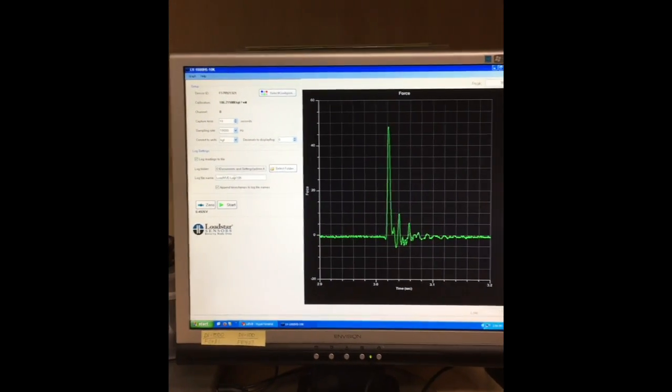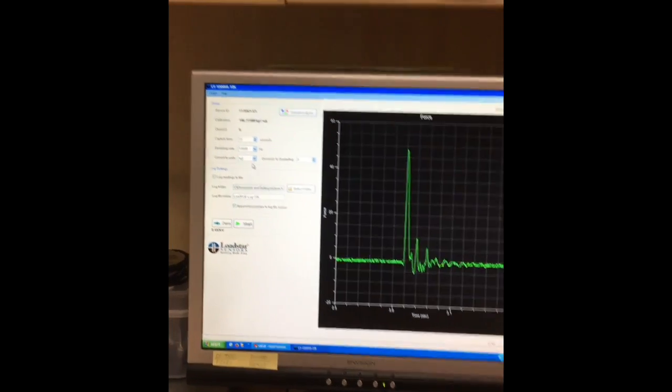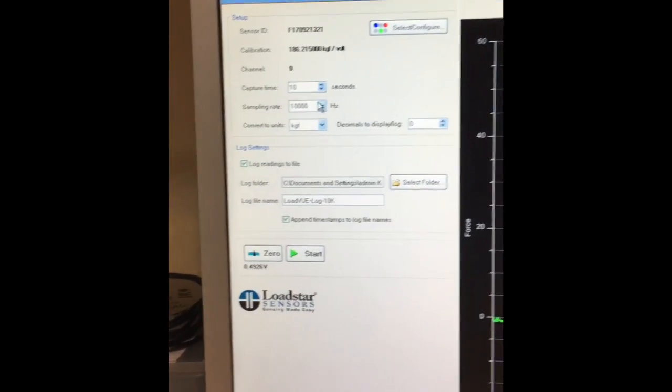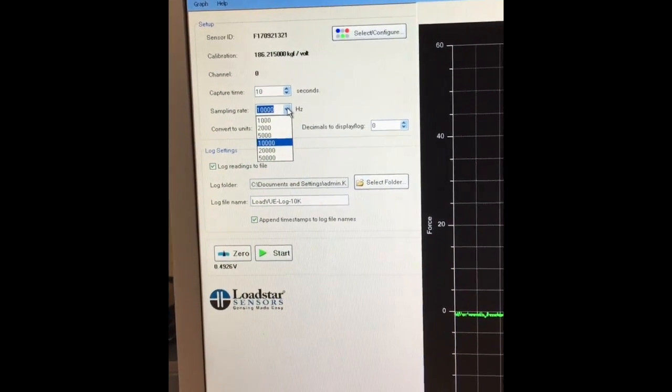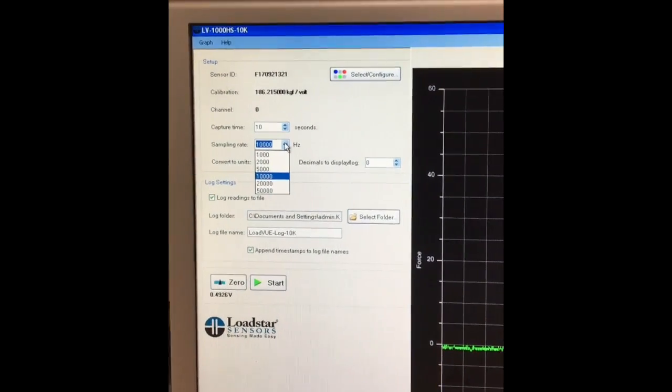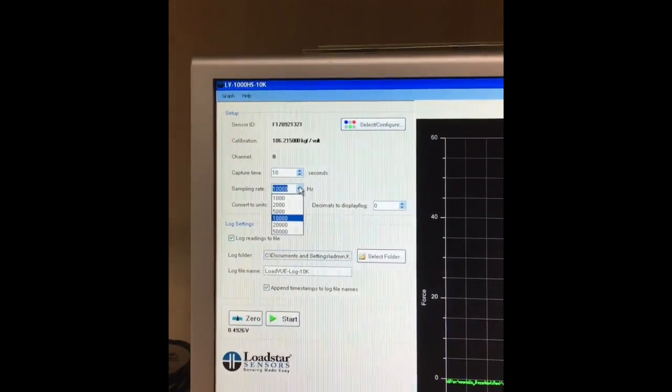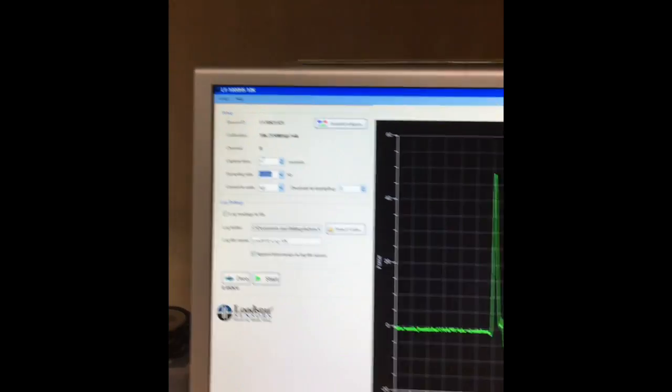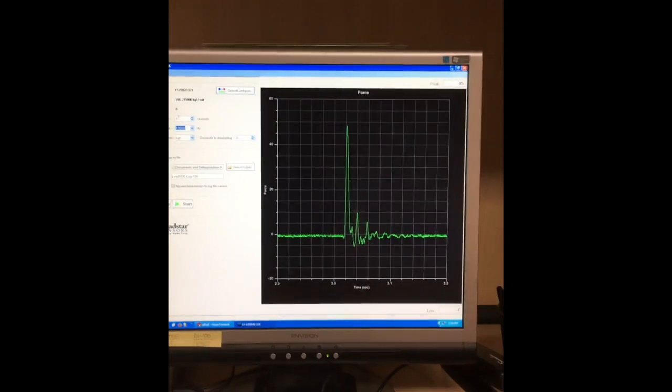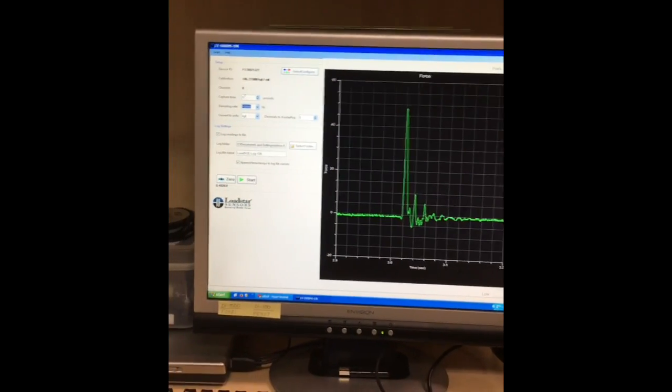You can change your file name, you can change the data capture rate. You can go as high as up to 50 kilohertz, but just remember that at higher data rates the noise can be higher and the amount of time for which you can capture will be lower. Just pick the appropriate parameters for your test.